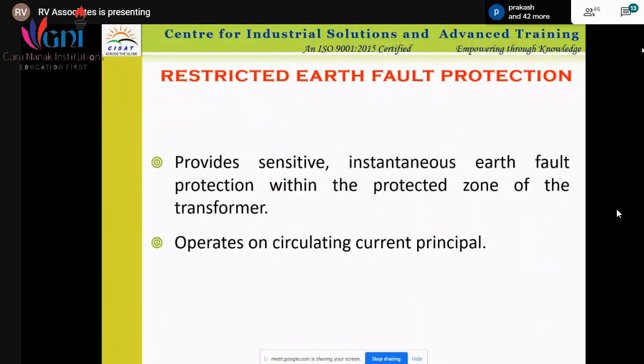Restricted earth fault protection is a type of protection. Again, it is an earth fault protection, but it acts within a particular area only of the transformer. Like differential protection, it will give protection for internal faults. Restricted earth fault will give you earth fault protection, but within a particular area. It can be maybe up to 10 meters, 20 meters area. That earth fault will be protected.